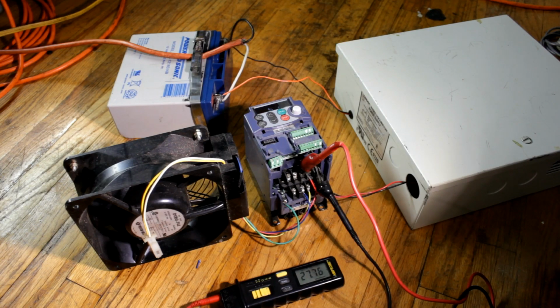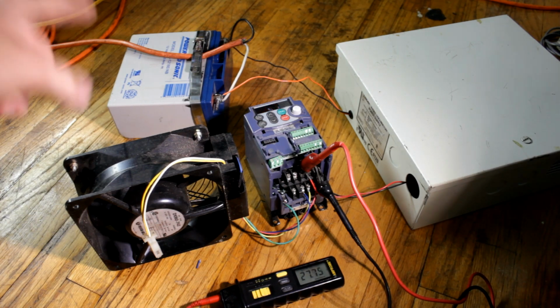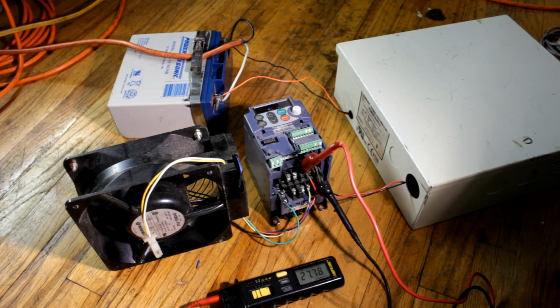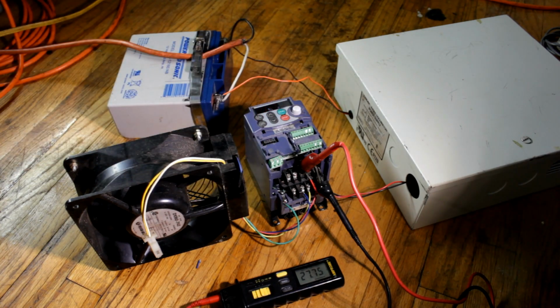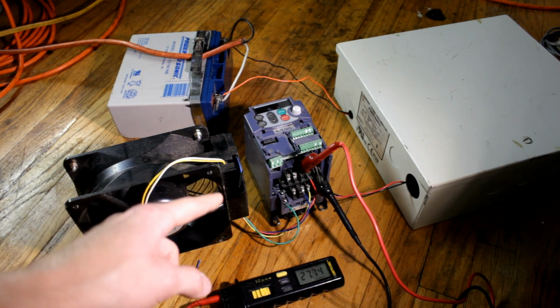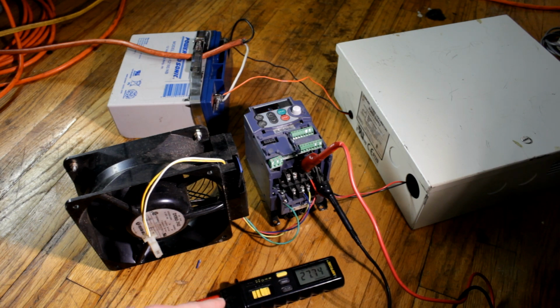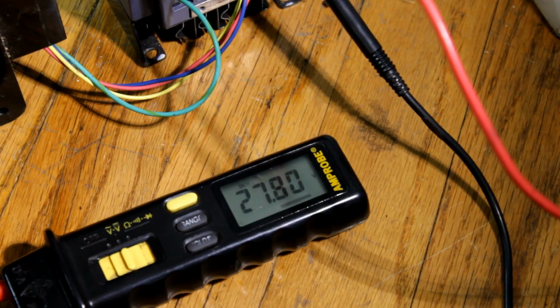Okay guys, just to prove a point, I'll show you this variable frequency drive running from direct current. That's the battery there, and that in the white box is a boost converter, so it just boosts the DC voltage up. It doesn't change it into AC in any way. The meter is hooked to the DC bus, and this is a three-phase fan we're going to run. So you see the boost converter is reading 27 volts DC.